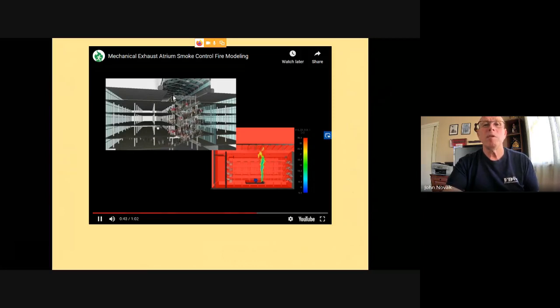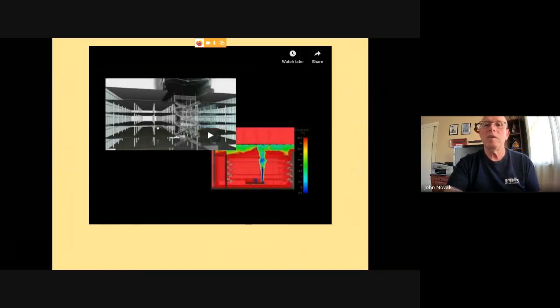It's supposed to keep the smoke level at least 8 feet above the highest level of occupancy. So this area up here, the smoke shouldn't come down below this area right here. And you can see the heat plume. So we're keeping this area here clear so the occupants can get to the stairwell and exit the building.